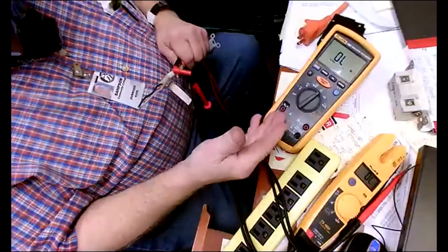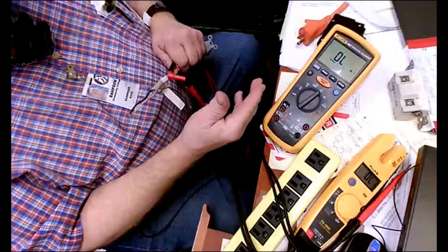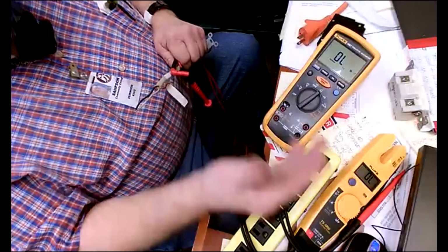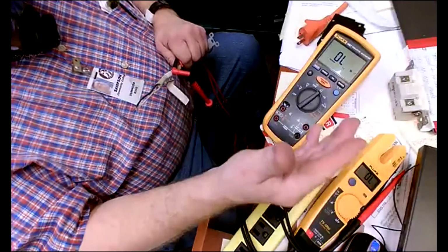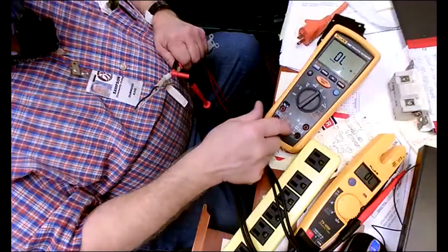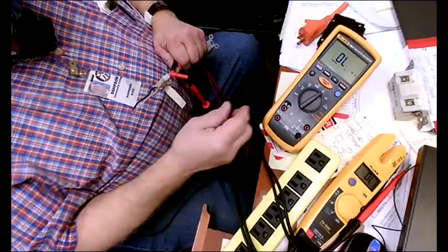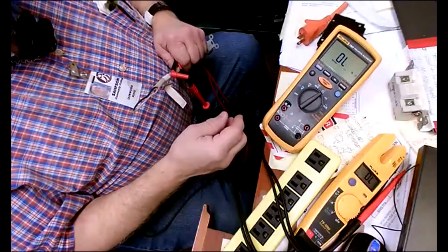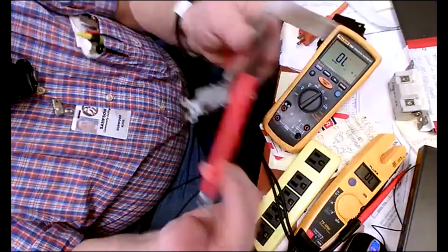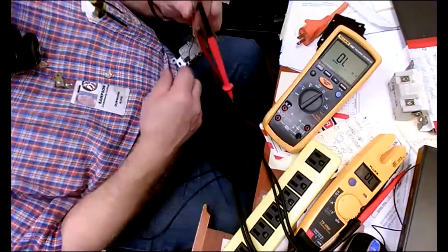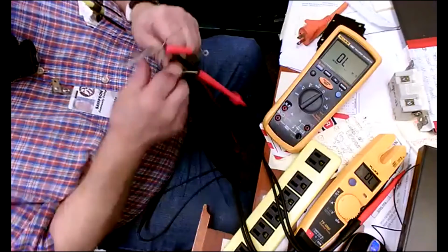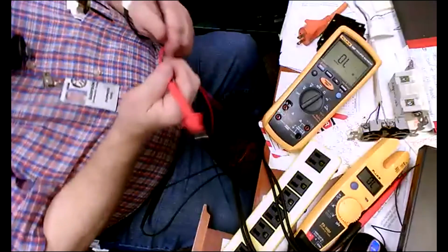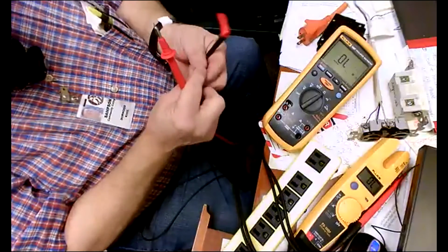Or try another set of test leads. Get a different set of test leads from somebody's meter and see whether it's the leads or the meter. I've had to send a meter off and get it worked on before, so don't assume it's the leads, because it may be the meter itself getting something wrong on the inside. That's a real possibility.